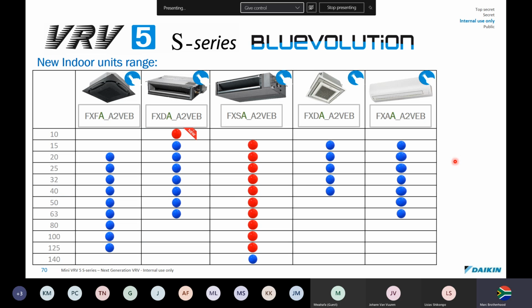These are the indoor units that have been designed specifically for the VRV5. Interestingly, they've gone right down to a 1 kilowatt ducted unit. This is because I realized that sometimes there's even a very small server room that might be very, very small, and a 2 kilowatt unit's even too big. So this is a new design allowing 1 kilowatt of cooling capacity and a low static pressure. But this is the range that you're going to get.